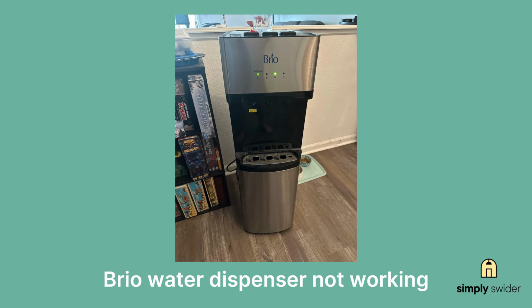Early warning signs to watch for: unusual vibrating or loud noises usually mean that pump's getting ready to go. And here's some free prevention advice. Give your unit at least 8 inches of space from the wall so it can breathe, and don't turn on those heating and cooling switches until the tanks have actually filled with water.